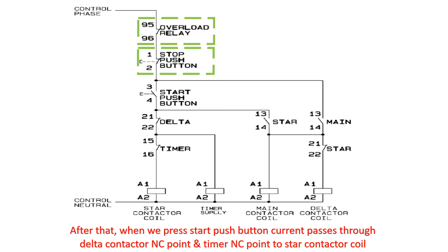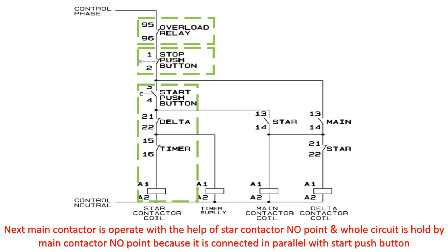When we press the start push button, current passes through the delta contactor NC point and timer NC point to the star contactor coil. Next, the main contactor operates with the help of the star contactor NO point, and the whole circuit is held by the main contactor NO point because it is connected in parallel with the start push button.